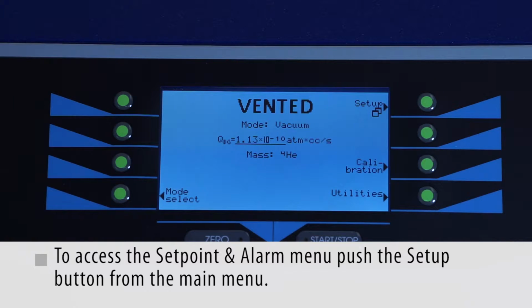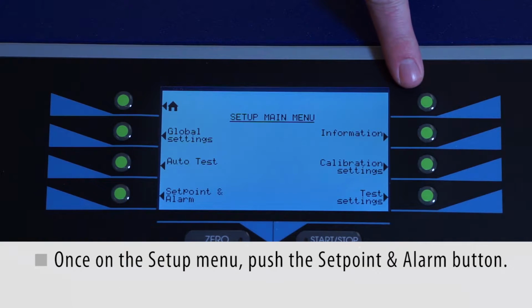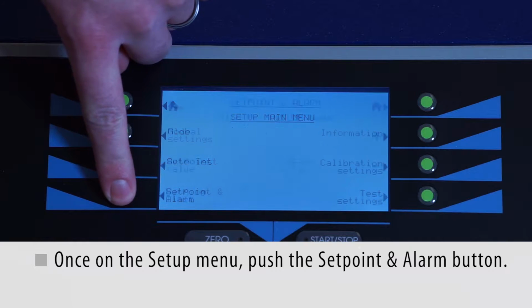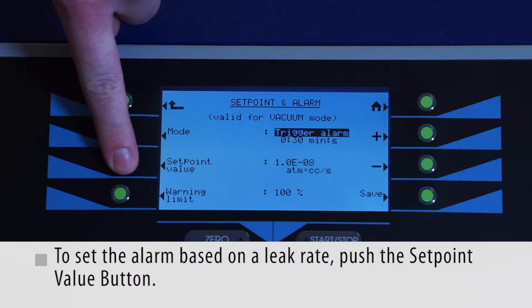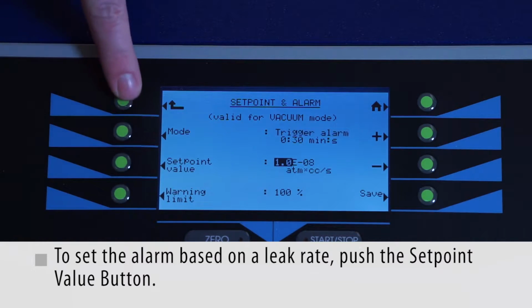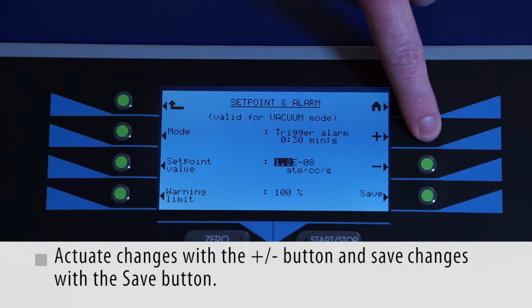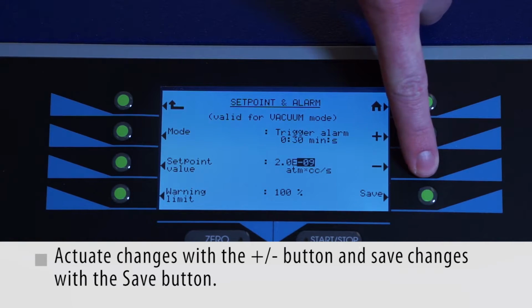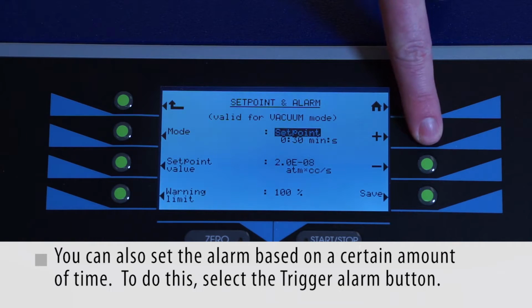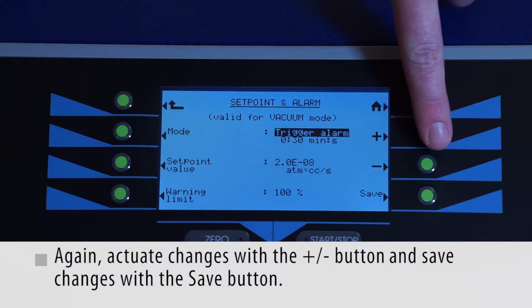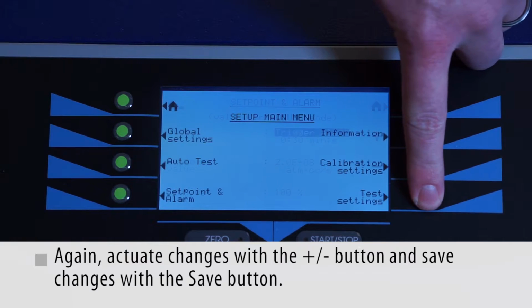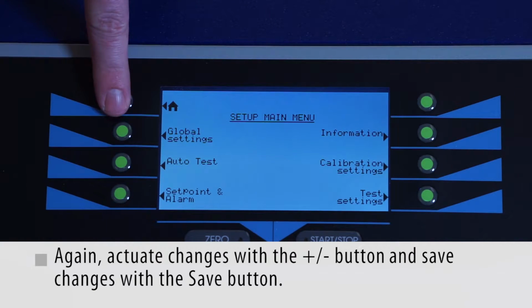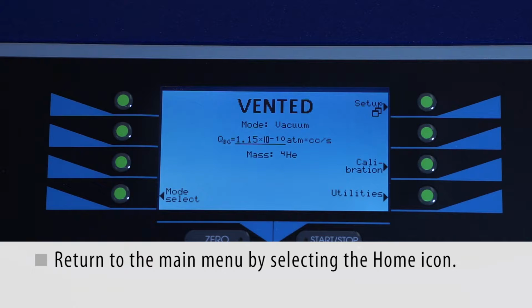To access the set point and alarm menu, push the setup button from the main menu. Once on the setup menu, push the set point and alarm button. To set the alarm based on a leak rate, push the set point value button. Actuate changes with plus or minus button and save changes with save button. You can also set the alarm based on a certain amount of time. To do this, select the trigger alarm button. Again, actuate changes with the plus or minus button and save changes with the save button. Return to the main menu by selecting the home icon.